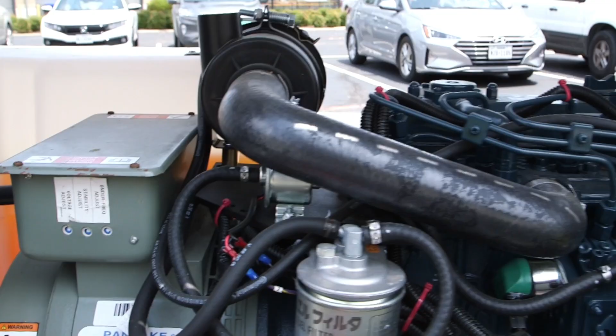On this particular generator, you have your air filter up top. It's very important to check those air filters and make sure they're clean. Once you check that, go ahead and move across the engine. You've got your radiator hoses, rubber hoses, and especially in this Texas heat and the heat of the generator itself, they will deteriorate quite quickly. So check those, make sure there's no deterioration, cracks, or anything of that nature.